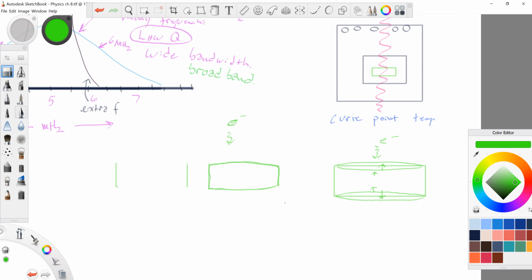When sound comes from below, let's say, comes back and runs into this guy, it's going to ever so slightly deform. I'll leave this one straight because it's deforming that side. Ever so slightly deform that element, and electrons are pushed away. And that is our echo. So our echo comes from here. This information is going to go to the computer for processing, and then eventually be displayed on the screen.